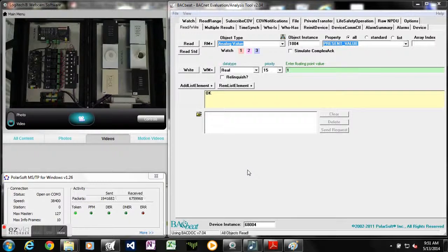Okay, the next object we're going to talk about is the analog value object 1005. And this is our scene trigger object. It's just like the 1004 object, but what the scene trigger object 1005 allows us to do is, currently we have essentially 4 stations here connected to our system. So if this is a small system, this was all we were going to ever do. The scene trigger object allows you to use those remaining objects. So we have the 8 objects per station, and it stops there. So we have our objects 1 through 32. So essentially station number 5 starts at binary input 33. So we have 33 through 128 not being used on this system.